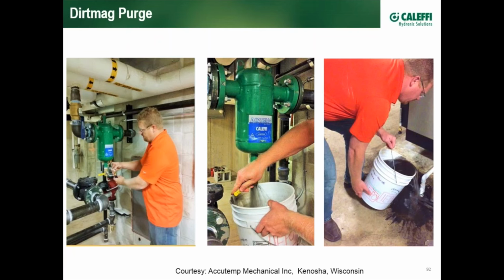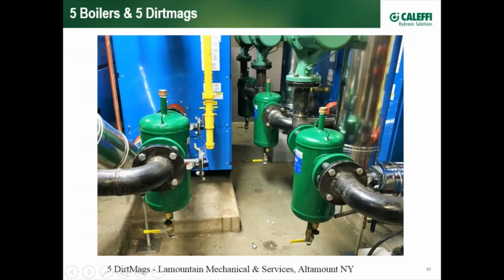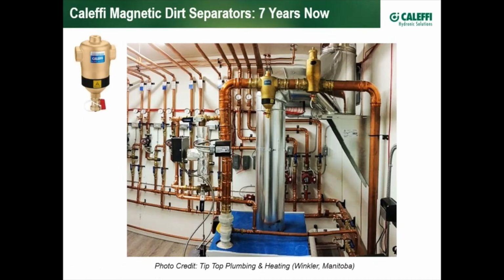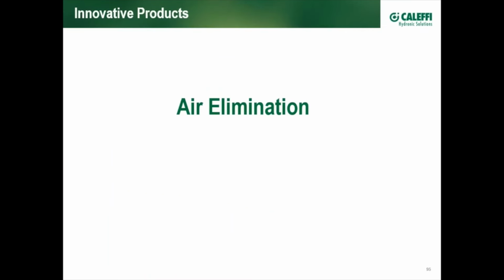Here is his third iteration. This was down in Kenosha, Wisconsin, and you can see when he blew down all of the magnetite that was captured rather than be allowed to create a problem in the system. Another shout out in New York recently submitted to us. These are five different boilers, five different systems, but all in one mechanical room, all being protected by a Caleffi magnetic dirt separator. This technology is very well proven. In the brass variety, we have had these in place for 7 years now, as shown here on this system up in Manitoba.